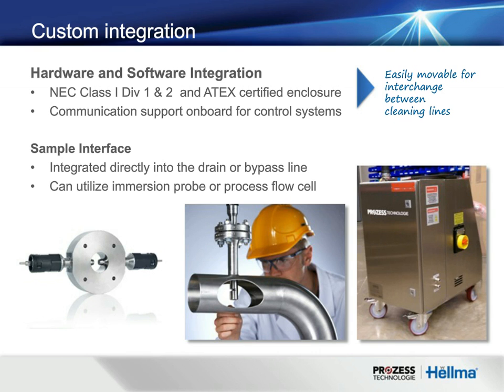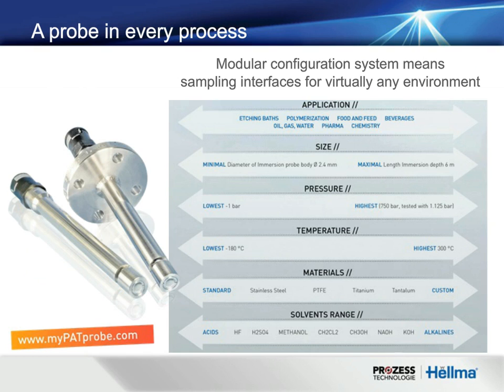Thank you, Chad. So as he said, this is typically integrated directly into the drain or bypass line for cleaning validation. Frequently, for other applications, we can integrate directly into continuous flow pipelines and batch reactors as well, using our fiber optic connected immersion probes. For 93 years, Helma has been making precision spectroscopic sampling accessories, and for the last 20 plus years, we have been designing, manufacturing, and advancing online process sampling with fiber optic connected immersion probes.